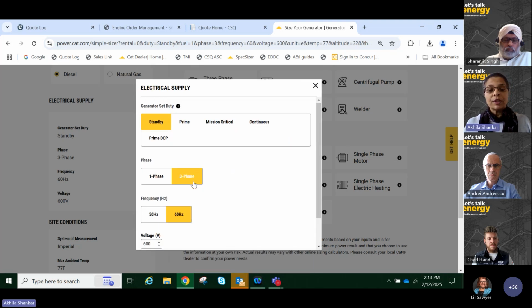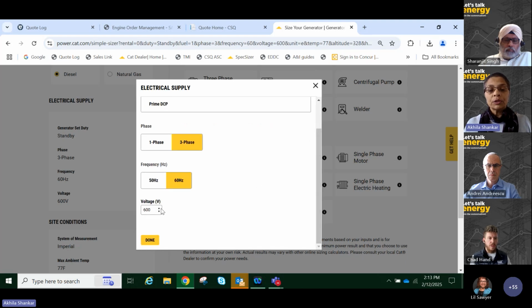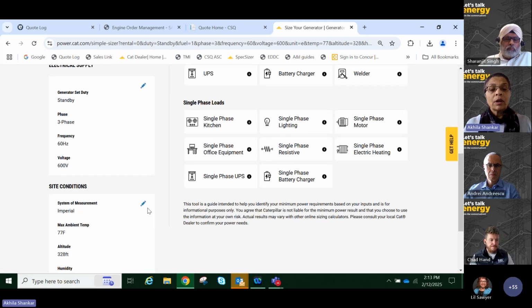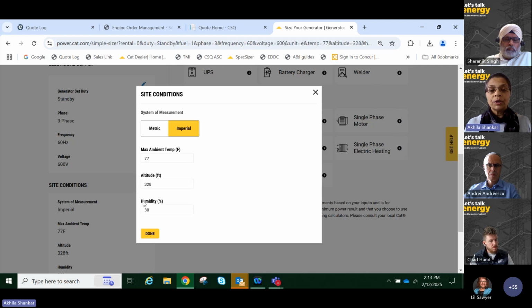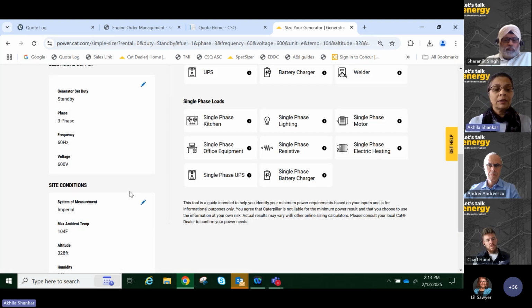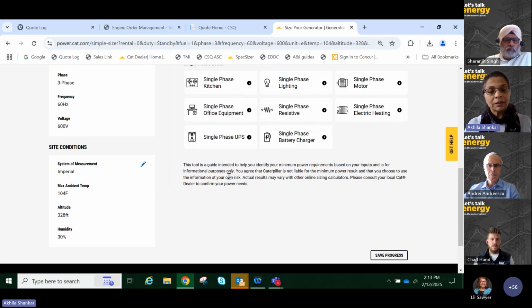Next you define whether it's a three-phase or single-phase genset and the frequency, and you can also choose the voltage for the generator set. We'll leave it at 600 volts for this exercise. Click Done, and then move on to defining the site conditions. Here you can choose the system of measurement, metric or imperial, and change the ambient temperature, altitude, and humidity as required for your site conditions. Once done, click the Done button.